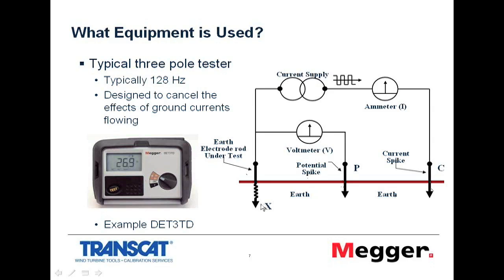The first connection, the X, is made to the earth electrode you're going to test. Second connection is potential. That is connected to an auxiliary spike or probe, which the operator will place into the ground. And then you've got the current spike or probe, which is placed again by the operator, and in this case the instrument is injecting a test current into the ground.